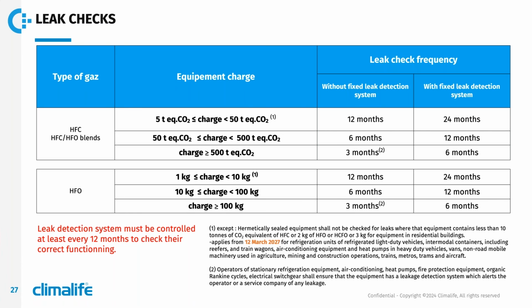Between 50 and 500 tons of CO2 equivalent, the frequency is every 6 months, or every 12 months if a fixed leak detector is installed. And when you have 500 tons of CO2 equivalent or more, the frequency is every 3 or 6 months. You have some exemptions and you have a new date for a new section, which you can read directly on the screen. A new rule appears.